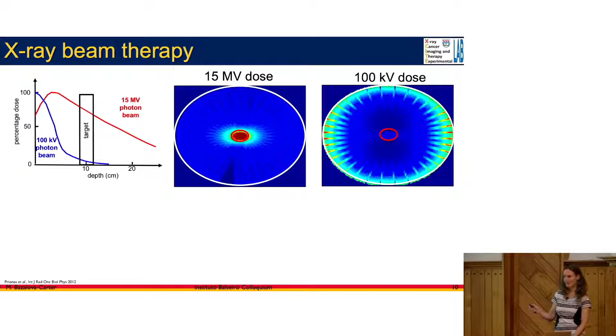Now, what happens if you look at a low energy beam? We talked about 15 megavolts, now we are down to 100 kilovolts. This is the dose distribution that we are getting, and you'll see that there's not very much in the target. Even if we rotate a single beam, this is what we'll get, and of course, the only thing that we will be doing in this treatment is just to burn the skin of the patient, and no radiation will be delivered into the target. So how are we going to do this?